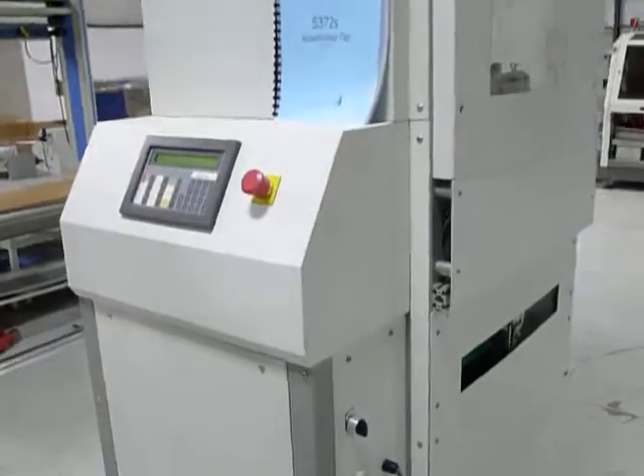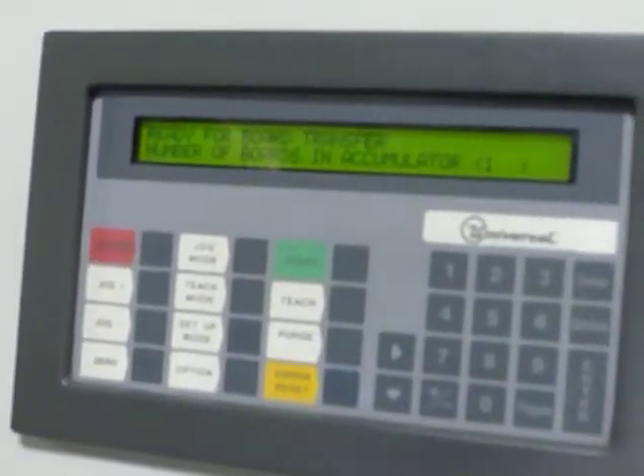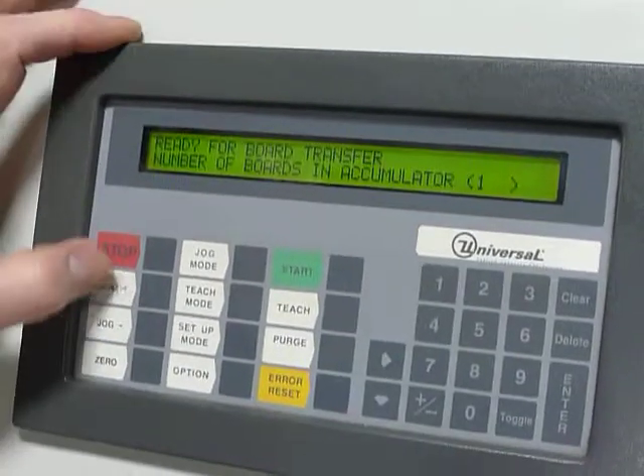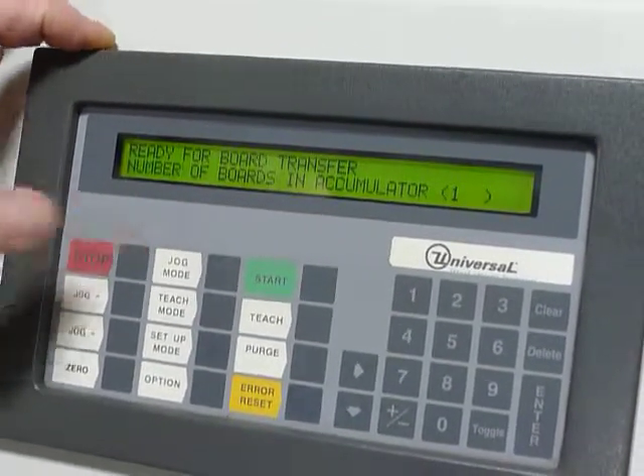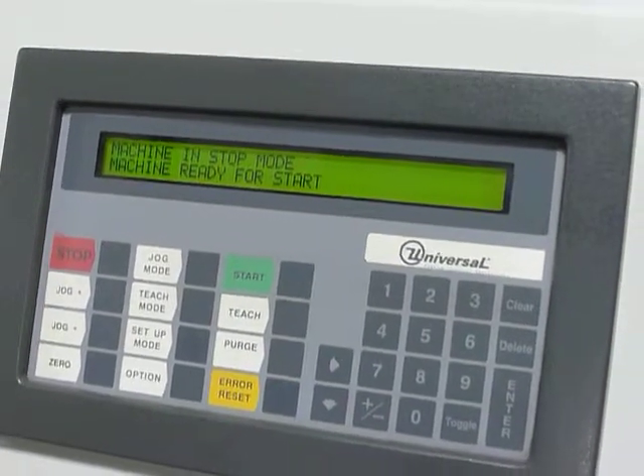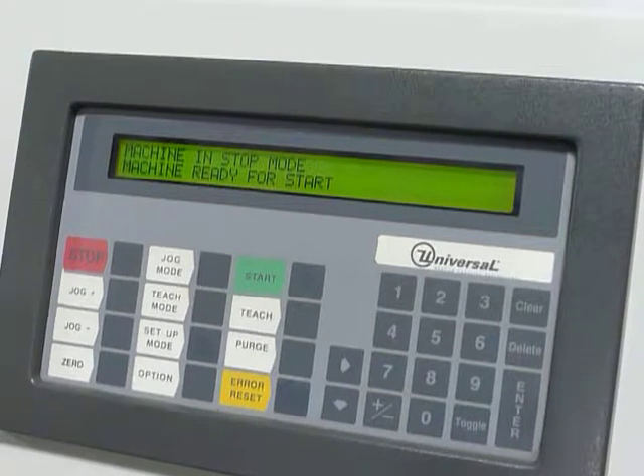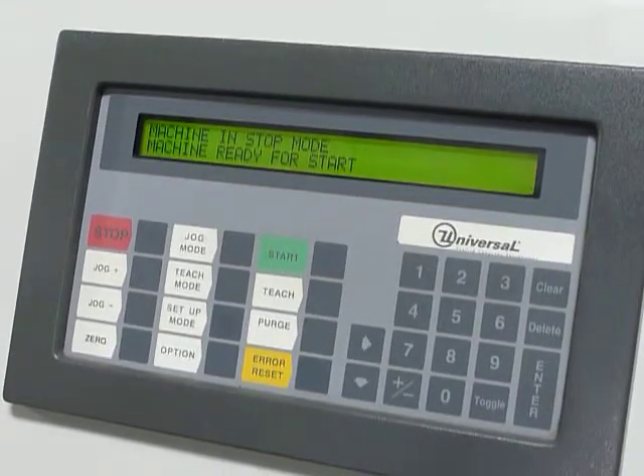I'm going to leave this one board in here. It's very important that the magazine is empty before you make a program change. If you do a program change and there are boards in the magazine, the machine will detect it and will want to go into a purge sequence, which will take a very long time. So it's best to make sure it's empty.